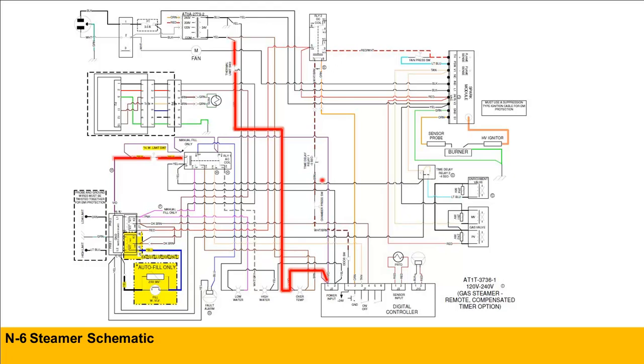So we've got the wiring diagram. The purpose of this is, obviously, sequence of operation and also troubleshooting. So that being said, if a safety has been tripped, obviously the unit's not going to heat up, and then we need to figure out which safety has been tripped. The easiest way is to look at the lights under the control display, which will tell you either an overtemp or a high water condition.